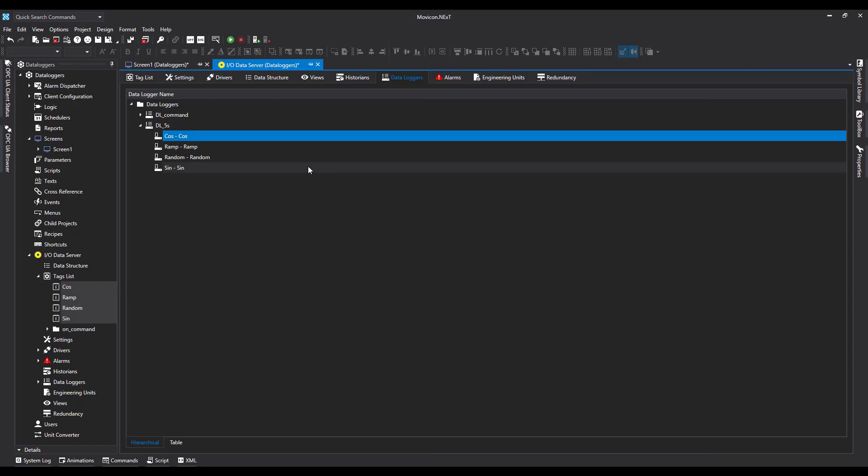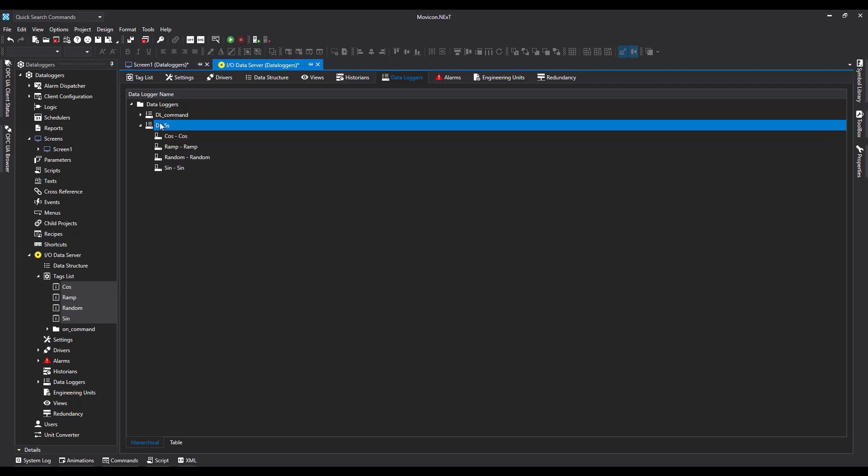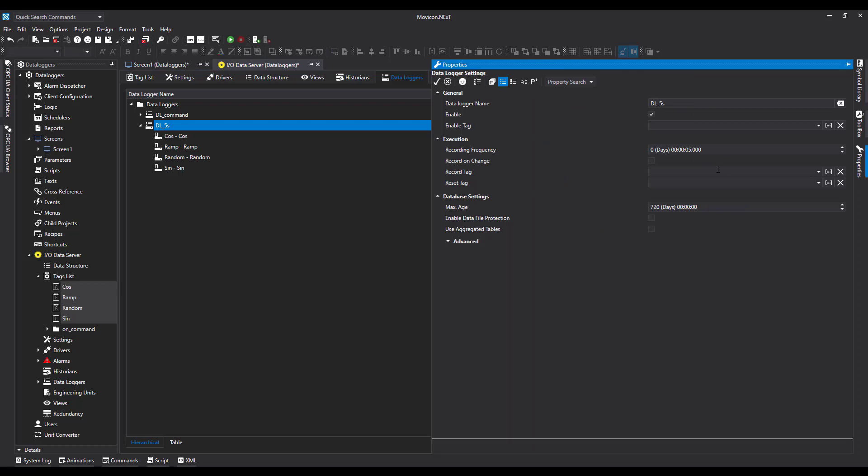Now because of the nature of this data logger, it's going to run every five seconds, 24/7. It may be a case where you only want to record information during a set process. For instance, you may want to check an oven temperature only when the oven is running. In this instance, we need to use a boolean tag to turn it on and off.